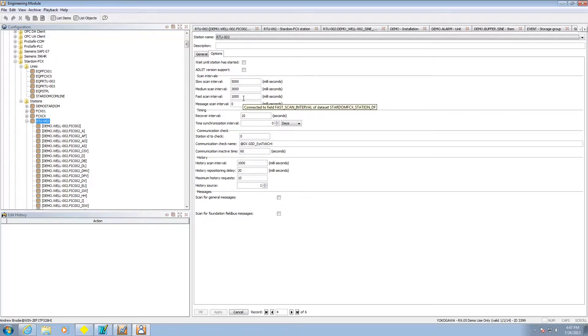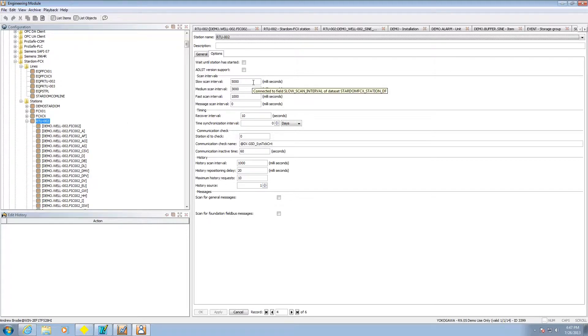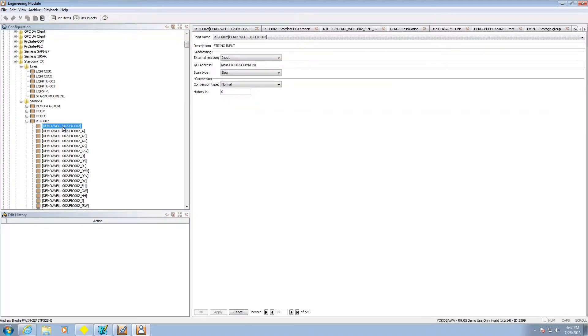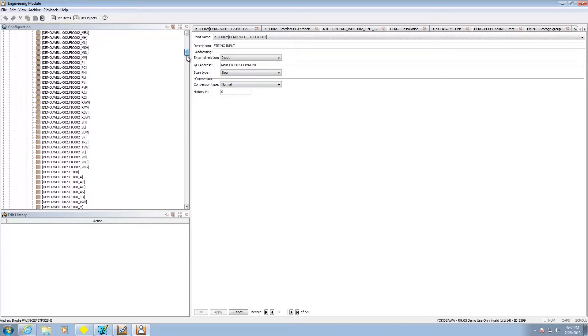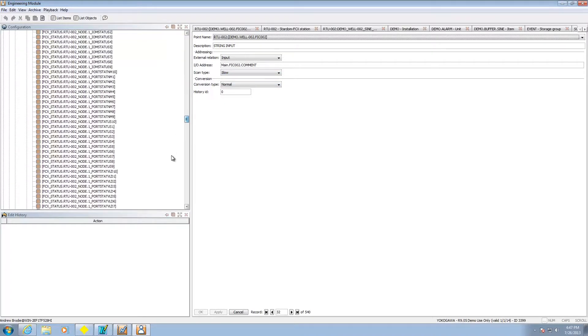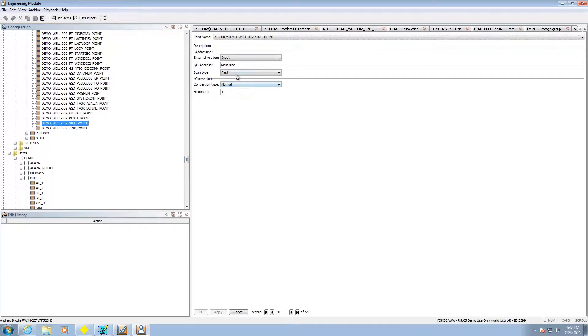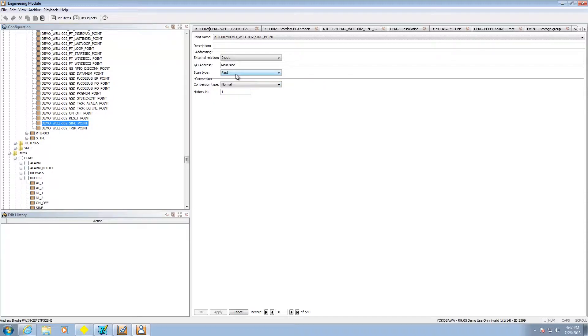These are very important because when you do an item you're going to pick one of these intervals. You're not going to be able to log any faster than you're scanning. In this case for this particular interval you can see I'm doing a slow scan type. One of the ones I was showing you on the screen was sine point. This guy's fast. If we flash back to a previous where I was showing you, the fast was actually at a thousand milliseconds or one second.